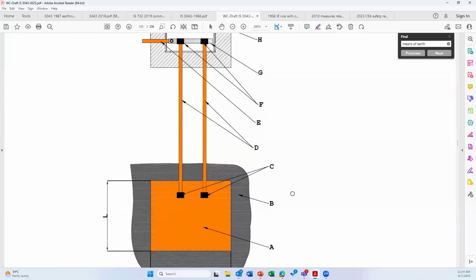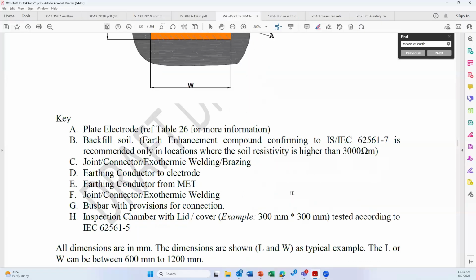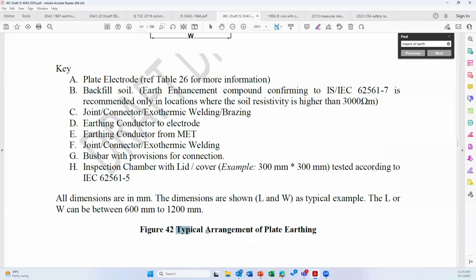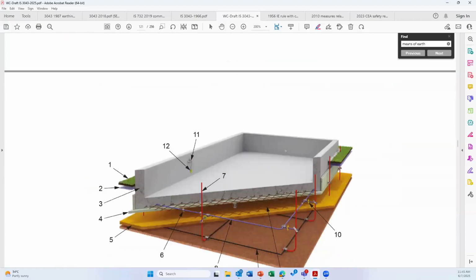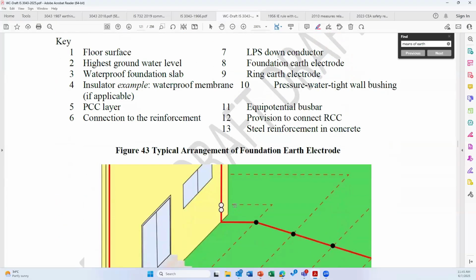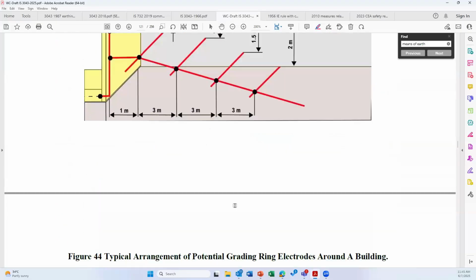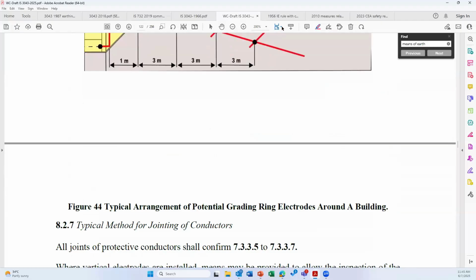Technically speaking, we have to be very careful in understanding these figures. Please note that these are typical arrangements of earth electrode. Sorry, not earthing. Typical arrangement of earth electrode. Typical arrangement means sometimes you may have to make an earth electrode and you can use this method. That is the meaning. Similarly, concrete embedded foundation earth electrode, potential grading, all these figures are being made with respect to earth electrode.